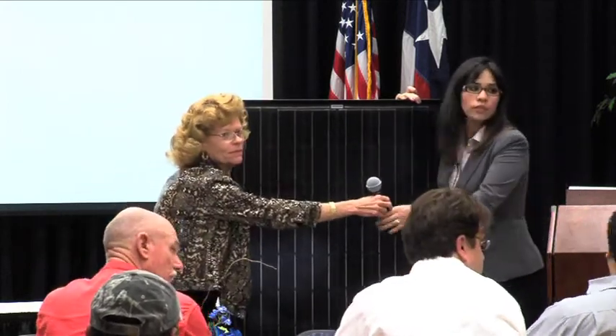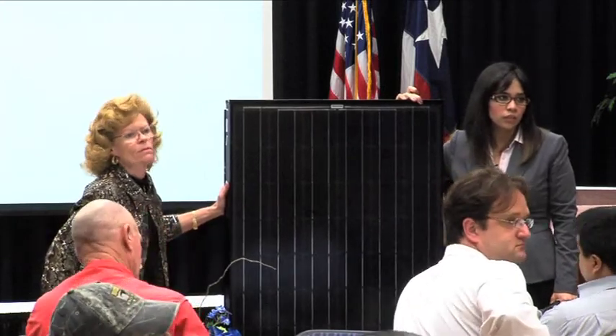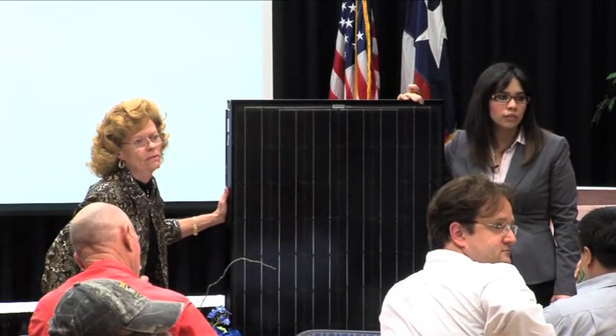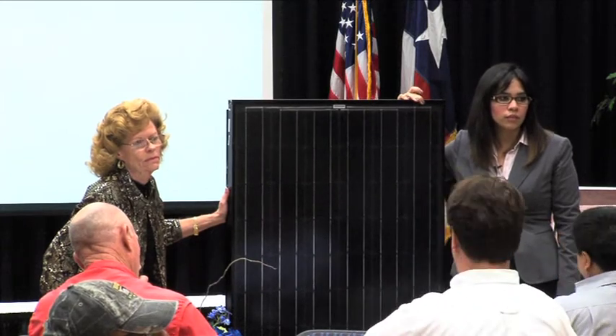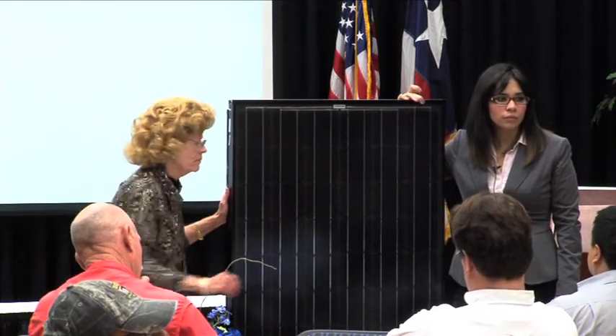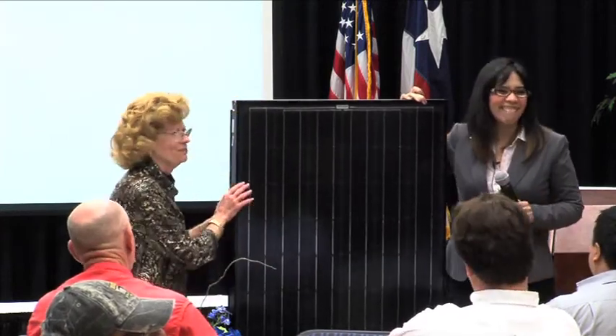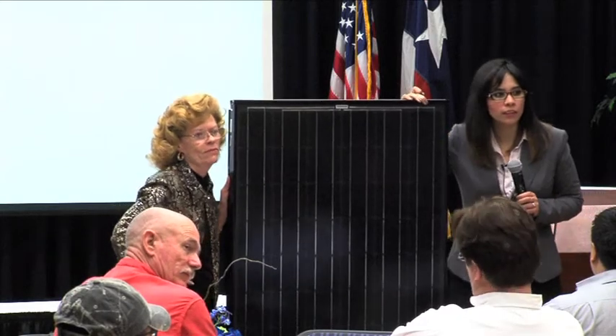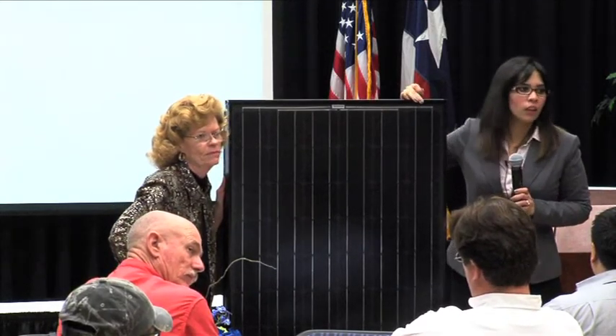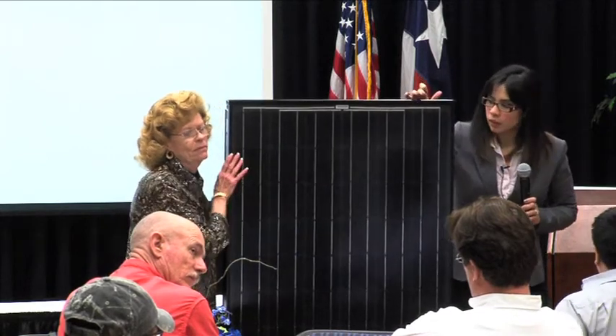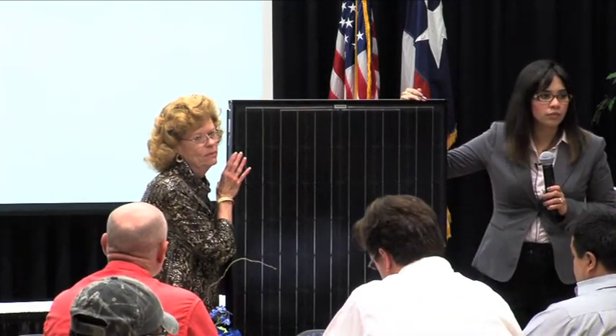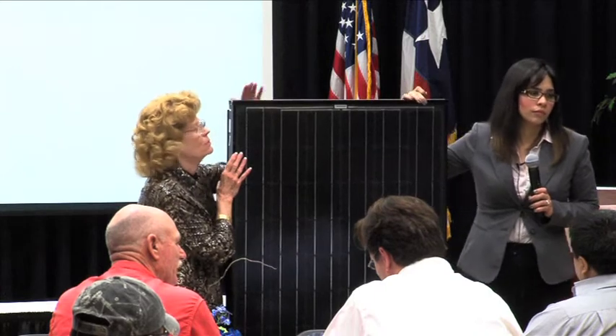Oh, I'm curious as to whether or not you have enough space to fit enough photovoltaic panels on the rooftop to power a 3-ton unit. For instance, this room, I'm going to guess, is 120 by 150 feet, about 18,000 square feet. Right. So I'm guesstimating it would use probably two 3-ton rooftop units, and each one of those panels generates 190 watts. Right, so 13 amps for each one of those rooftop units times 208 volts, 3-phase, would be about 4.6 kilowatts. So if I have it figured out correctly, that'd be about 25 panels for each unit.